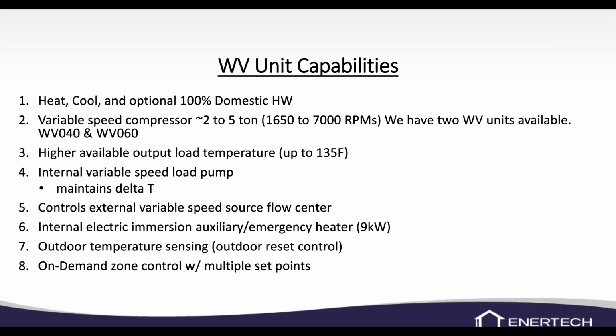We have an on-demand zone control with multiple set points. Basically what that means is if you've got a radiant zone, the hot water for that radiant zone may be a different temperature than what you get if you have a hydronic air handler. Obviously, in a hydronic air handler, we're going to want warmer water temperatures to get more heating capacity out of it. We may not want that in the floor, because the floor may have, let's say, a max of 90-degree water. So we wouldn't want to send 120-degree water to a floor zone that the max that it wants to see is 90 degrees. So the controls will realize if it's a hydronic zone call, or a radiant zone call, or a forced air zone call into the zone controls, and then it'll base its temperature output on what call it's receiving.